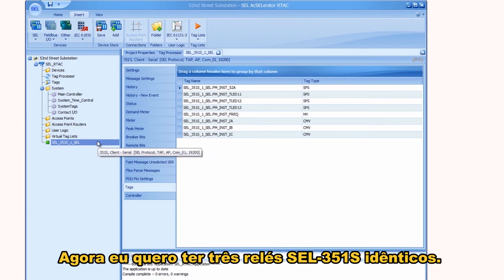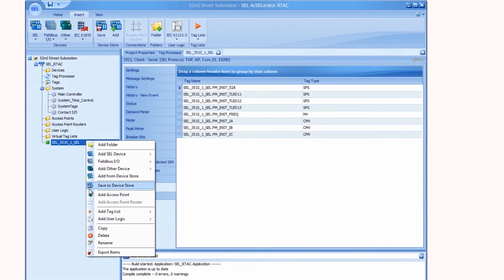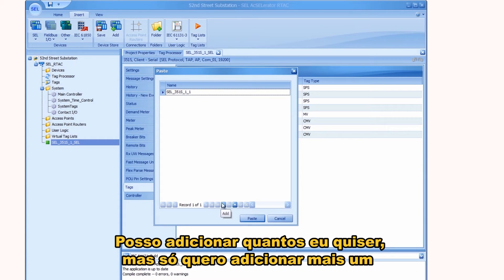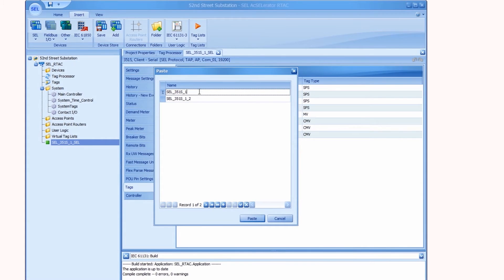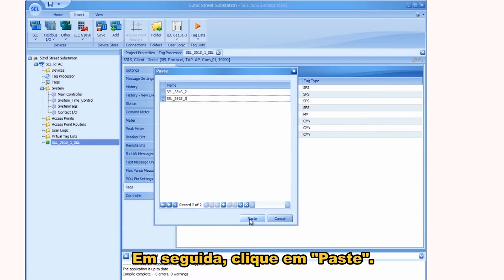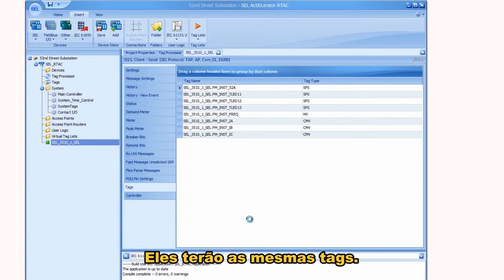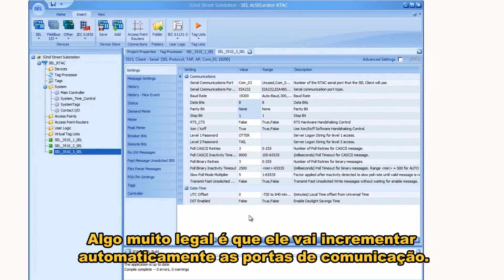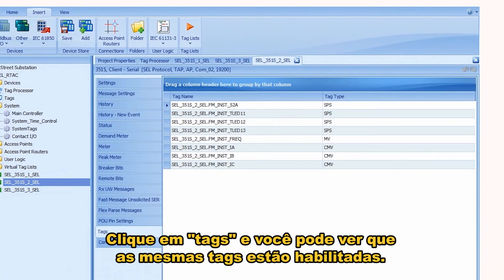Now I want three 351Ss that are exactly the same, so I right-click and select Copy, then Ctrl+V to paste. I'll add one more — naming them 351S-2 and 351S-3 — and paste again. This makes exact duplicates with all the same tags and communication parameters, except the really cool thing is it automatically increments the COM port. So device 3 gets COM port 3, device 2 gets COM port 2, and you can see all those same tags are enabled.